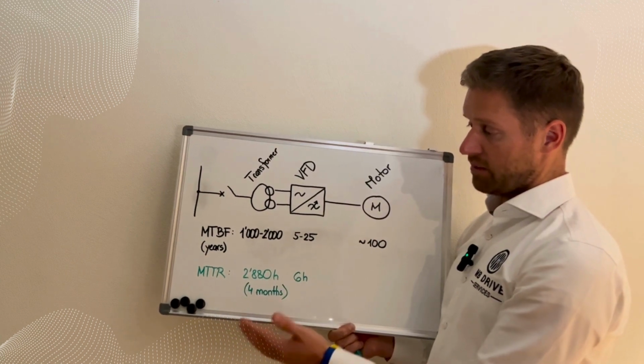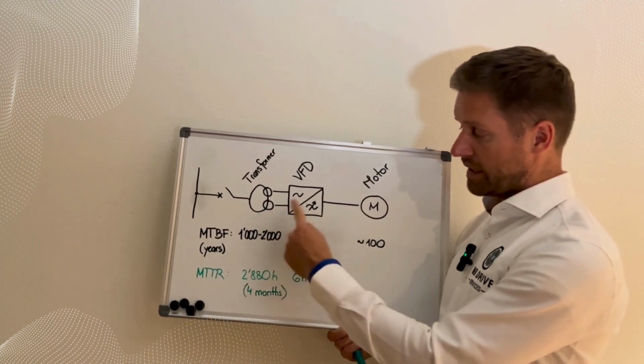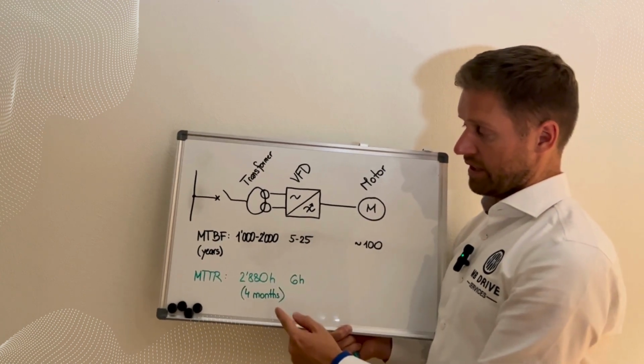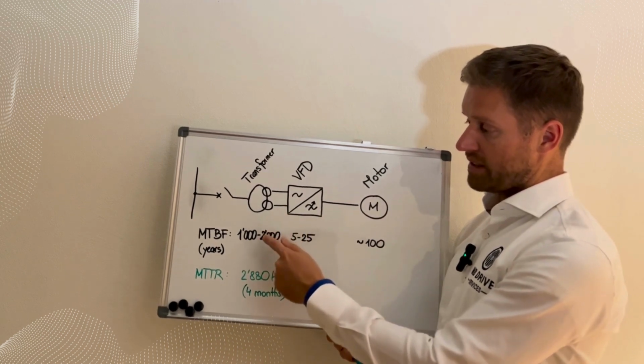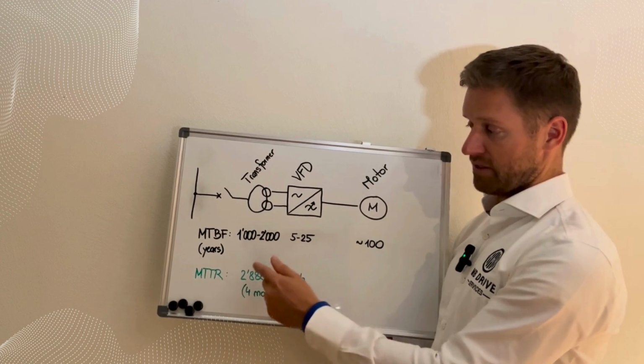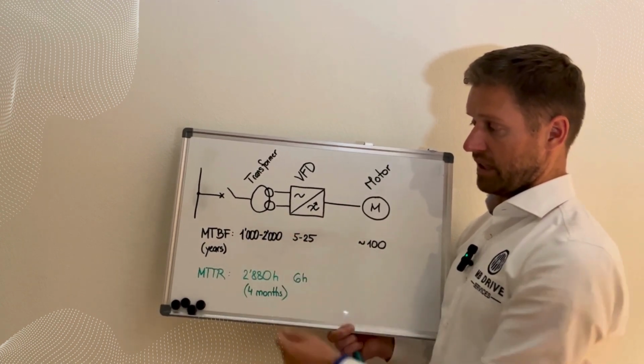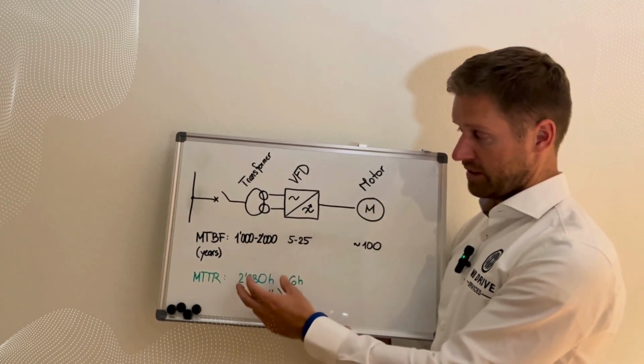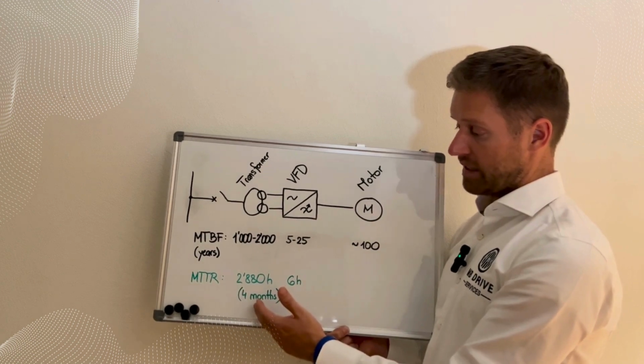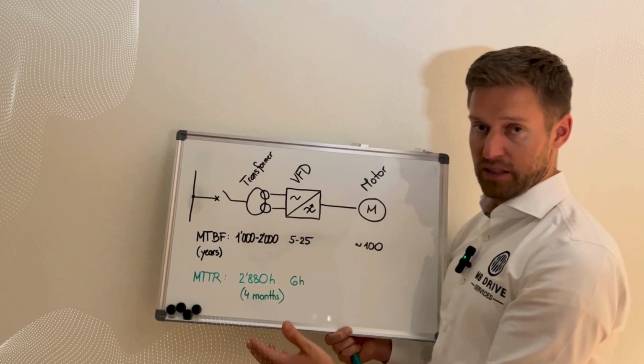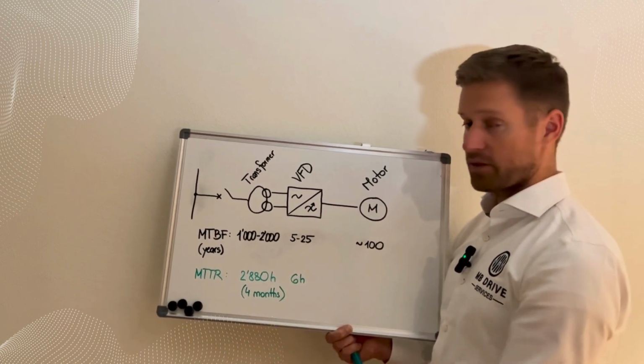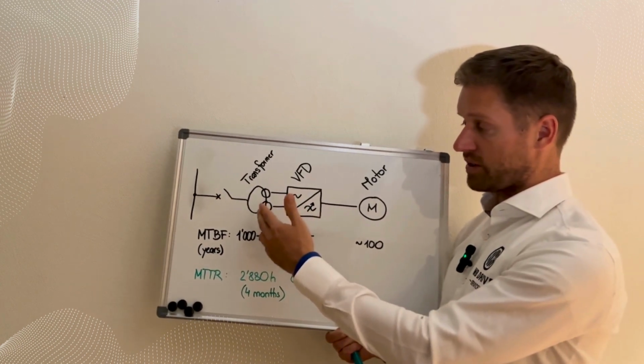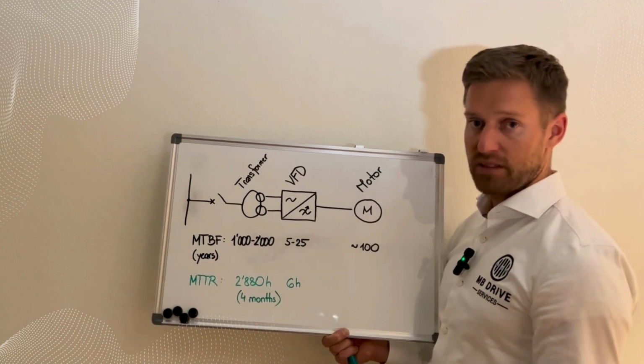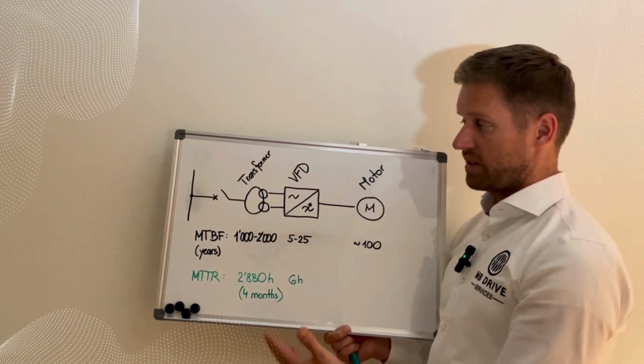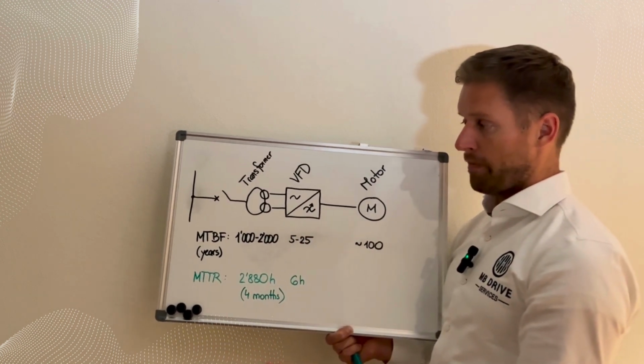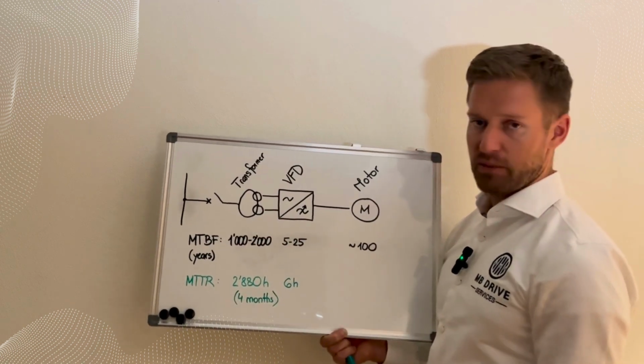Now what does it mean for the availability? What those figures tell you is basically that the probability that the transformer has a failure is very, very low. That's why the MTBF is very high. On the other hand, when a failure on a transformer happens, the repair often takes a significant amount of time, in terms of weeks or even months. If you have an internal short circuit in the transformer, it depends how quickly you detect it and how severe the damage is. If the winding is damaged, normally you cannot repair it on site.